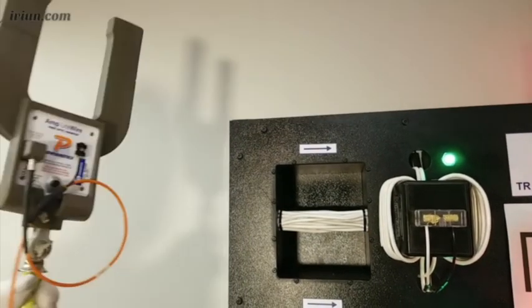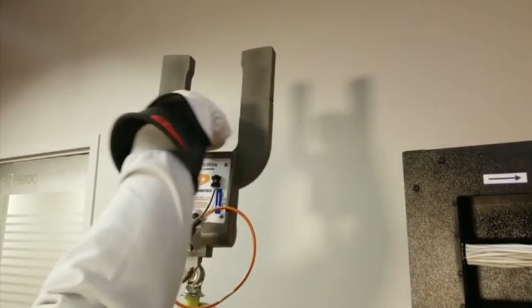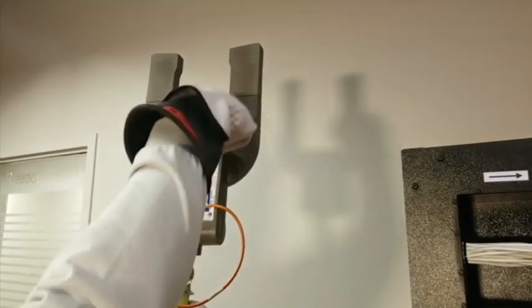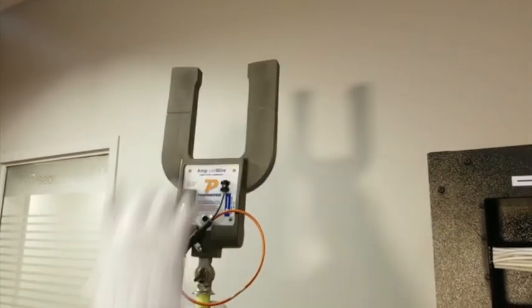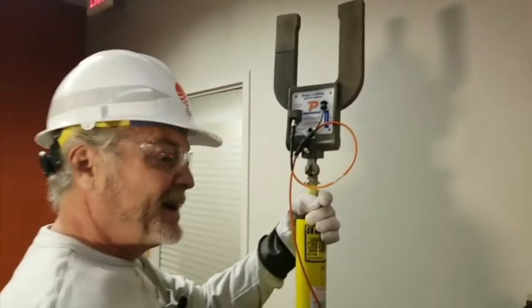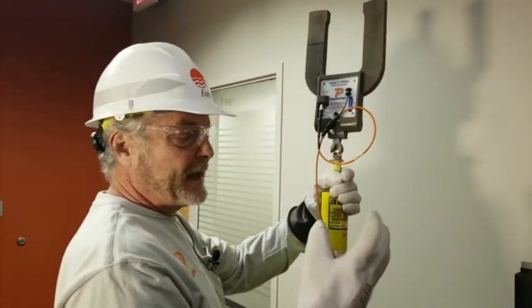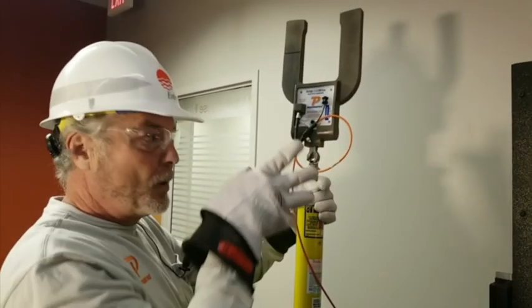Okay? You also have this line right up here. You want to try and keep your conductors inside of here. That's where this probe is most accurate. You get outside of here, things can start getting wonky on you. You want to keep it inside of here if you can. Okay? I also know that if you get a pole that is super tight and super populated, I got PTs, CTs, and it's all vertical, and everything's coming up like this, and I'm like, what in the world?